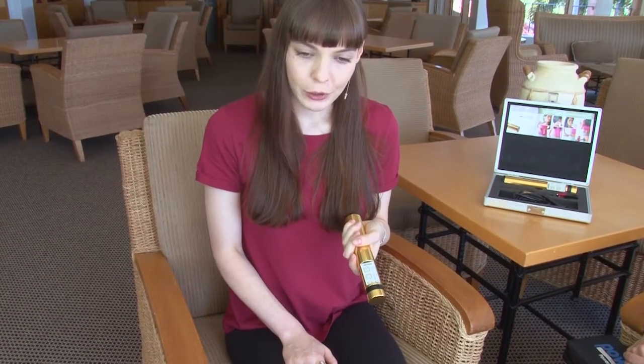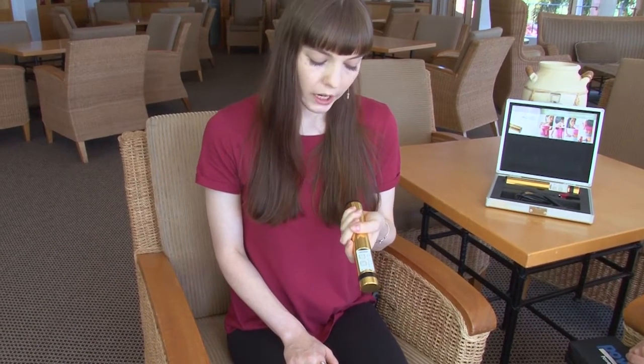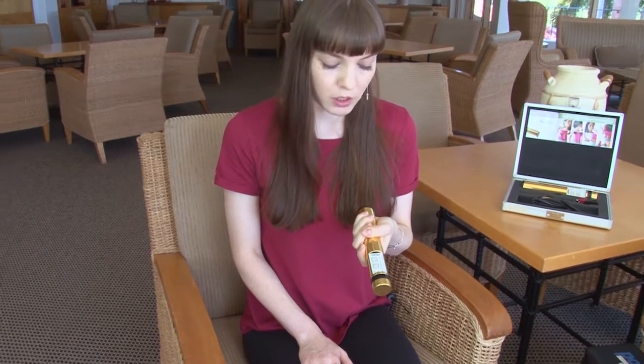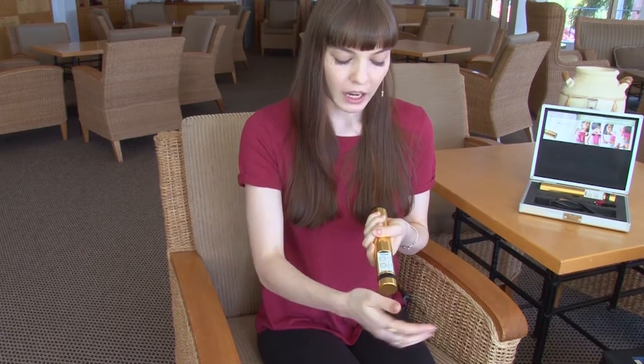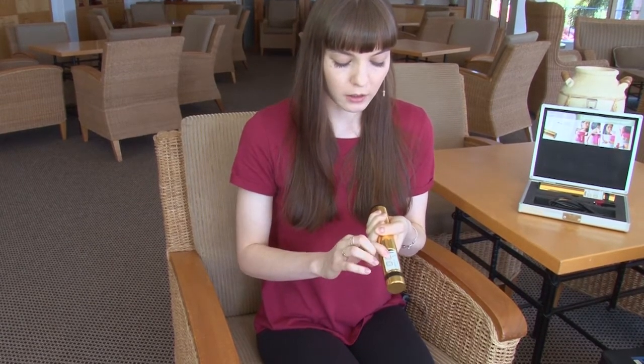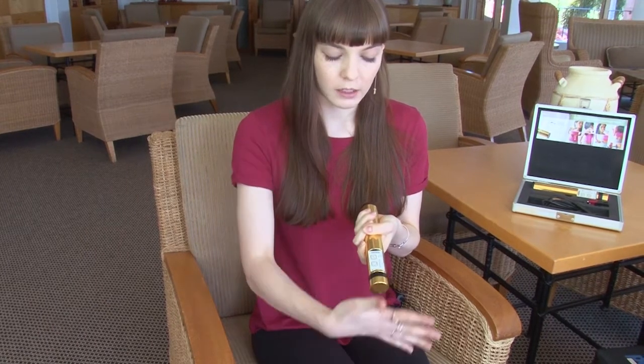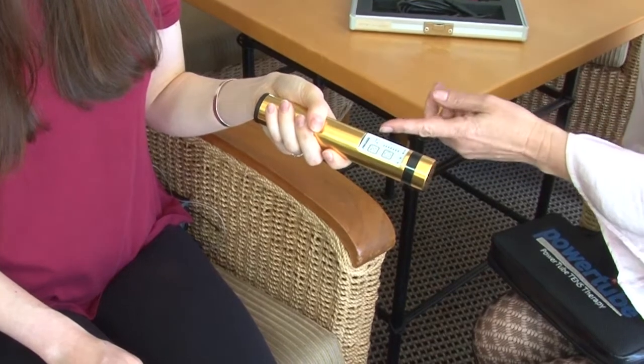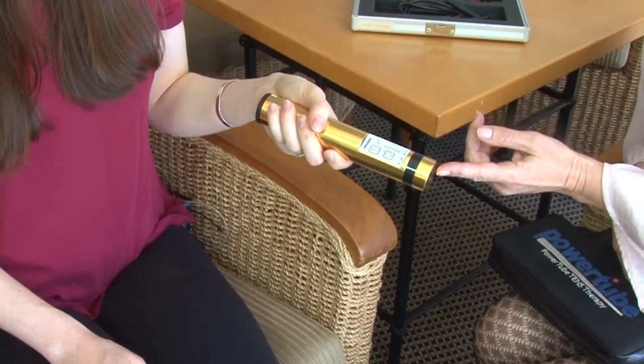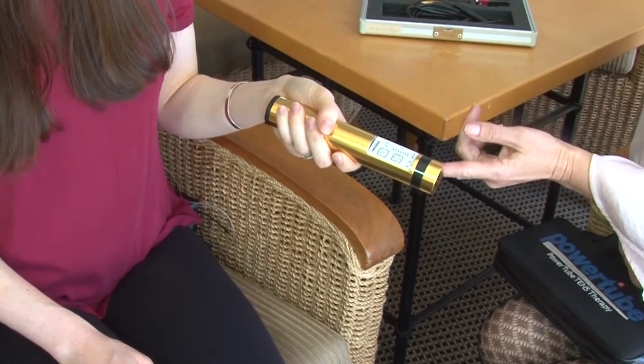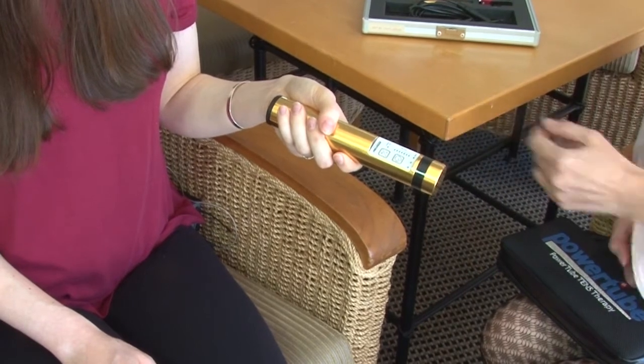It is important to know how to grip your device correctly. One hand should always be around the shaft of the device, and the other hand or body part must be connected to the bottom. If it is not connected properly, your device will continue to beep. If you are connected, the beeping will stop. The PowerTube works on high-frequency alternating current, and the black is the insulator between the currents.